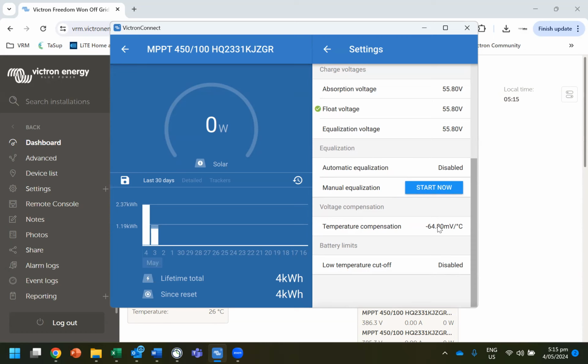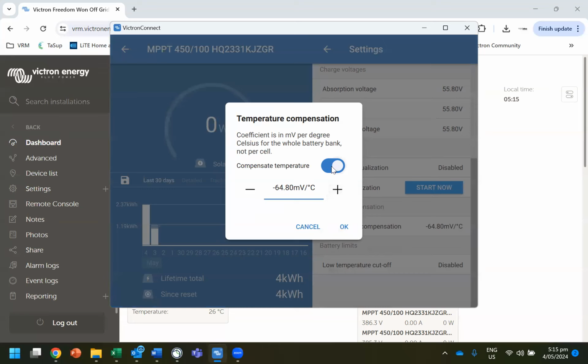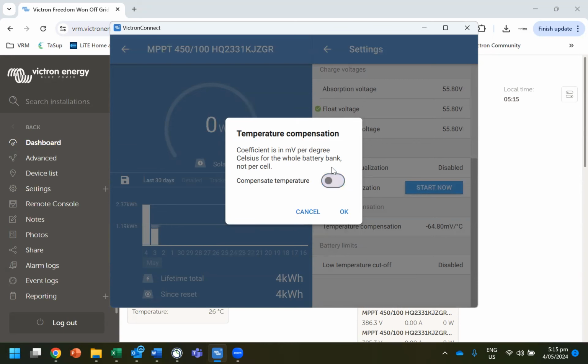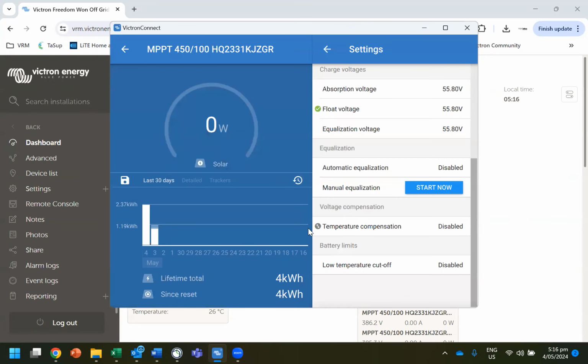Temperature compensation should be disabled, because temperature compensation is only used for lead acid batteries. There's a few other battery types that need a different voltage based on whatever the ambient temperature or the cell temperature is. Lithium, it's the same voltage for charging and discharging, in this case charging because it's a charger. So you don't use temperature compensation. So you're going to disable that. And again, we're going to look for that little tick, and there it is.